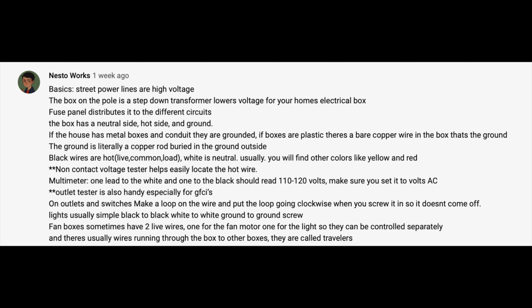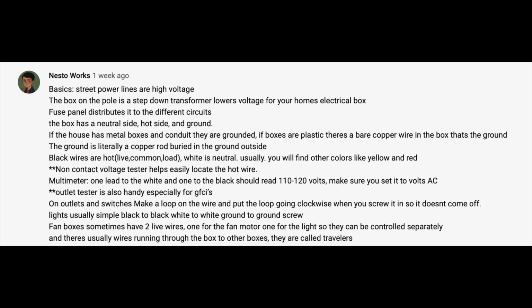Black wires are hot. They can also be called live, common, load. White is neutral. Usually you will find other colors like yellow and red. A non-contact voltage tester, like that pen I have, helps easily locate the hot wire. Yes, it beeps red when it's hot. Multimeter, one lead to white and one to black, should read 110 to 120 volts. Make sure you set it to volts AC.